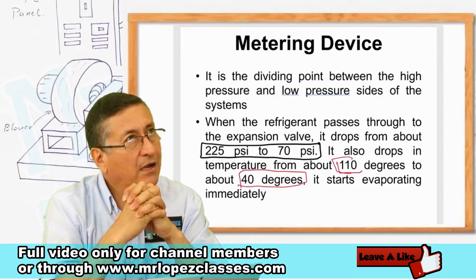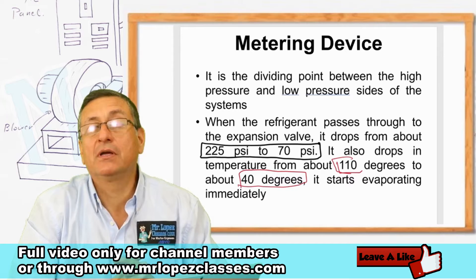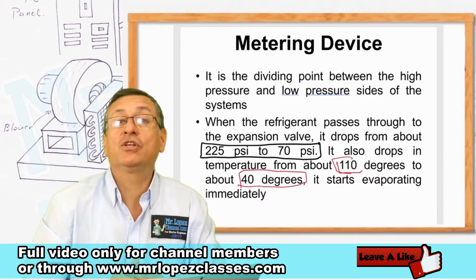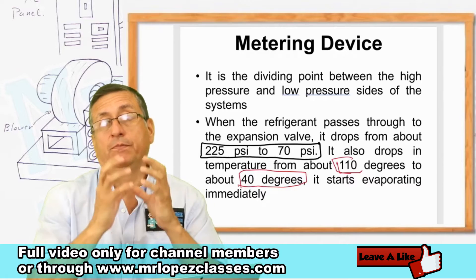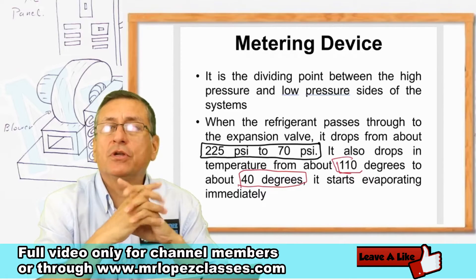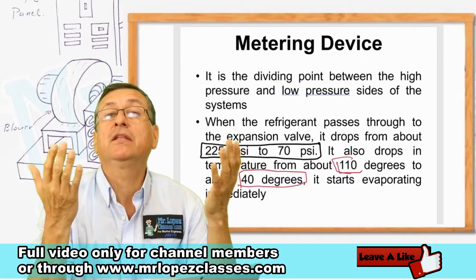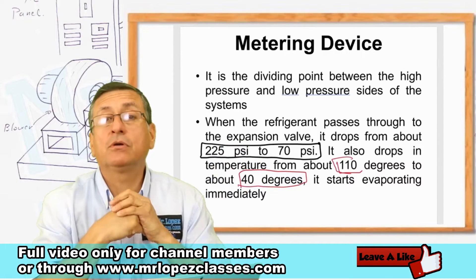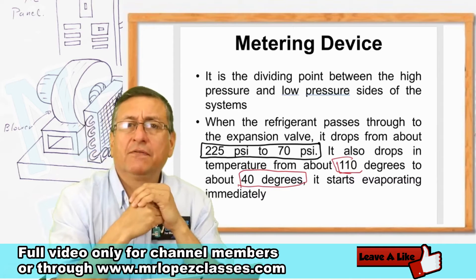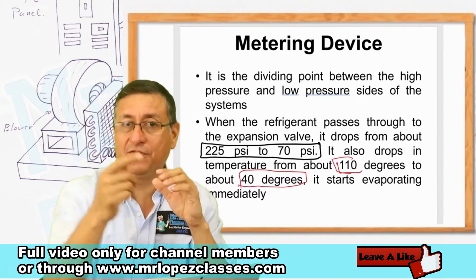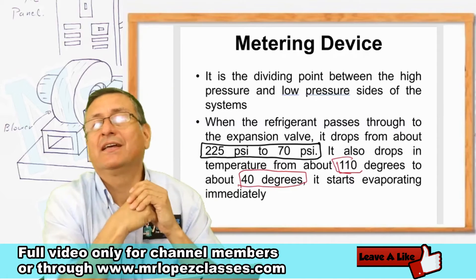After the expansion valve the pressure is around 60 to 70 PSI — a huge reduction in pressure, and also a huge reduction in temperature. At the input of the expansion valve the temperature is around 110 to 115 degrees Fahrenheit, and at the output it is around 40 degrees Fahrenheit.